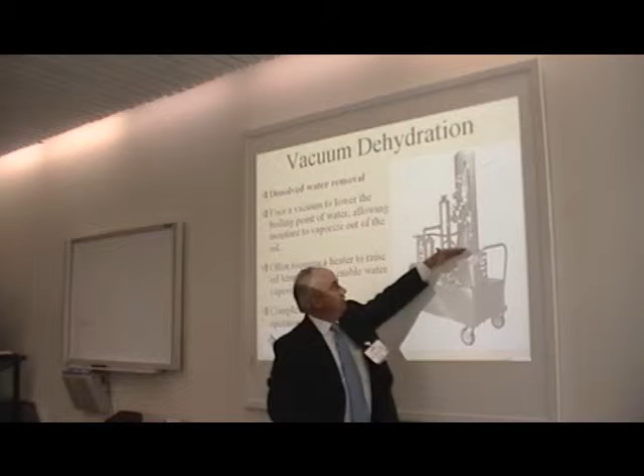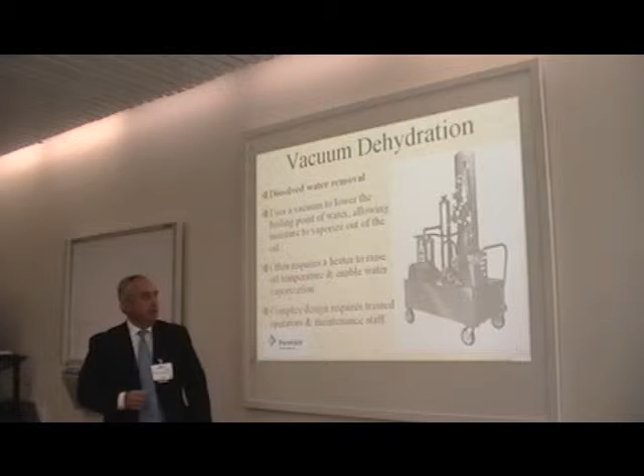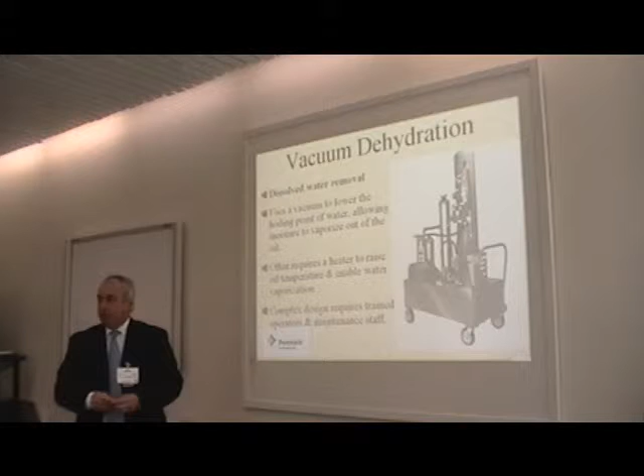The difficulty is they're very challenging to operate from most plant standpoints. They're expensive. They take a technician with a very strong core set of skills, and that person needs to be available to run it whenever you need it. The other challenge is if there's really gross amounts of water, they may have trouble keeping up. They can boil off a fair amount of water, but if it's hundreds of gallons, like in a major turbine upset, you can end up with so much foam forming through the vacuum tower that it actually starts foaming off the top, and now you've got oil going into vacuum pumps, oil hitting the floor. So they're very complicated devices that take a good skill set to use, and quite frankly, they're just not operator friendly.